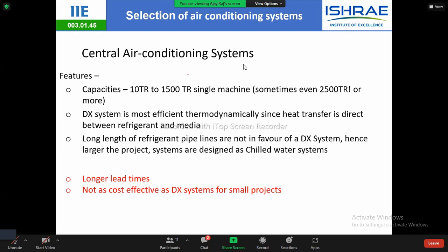Again, for small projects, I agree. A chilled water system may be expensive, but if you compare apple to apple, VRF system vis-a-vis chilled water system, you'll find the chilled water system is cheaper than your VRF system. Whereas in VRF system, most of the manufacturers give you a discount as high as 50% also. In spite of those discounts also, there's a possibility that your chilled water system may be cheaper than your VRF system.